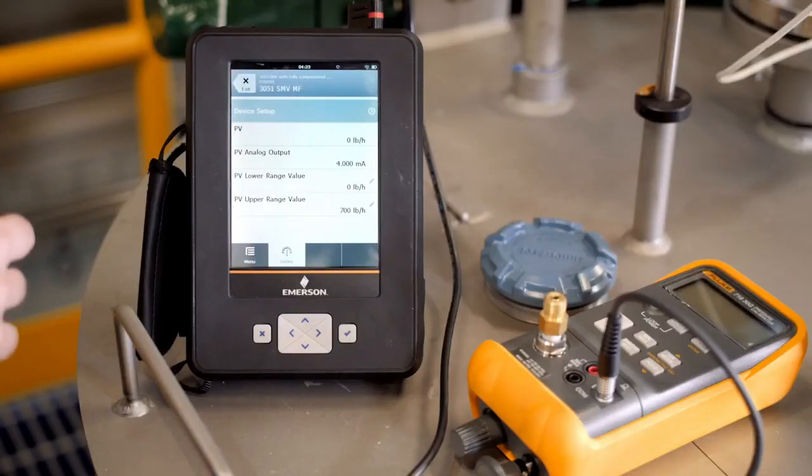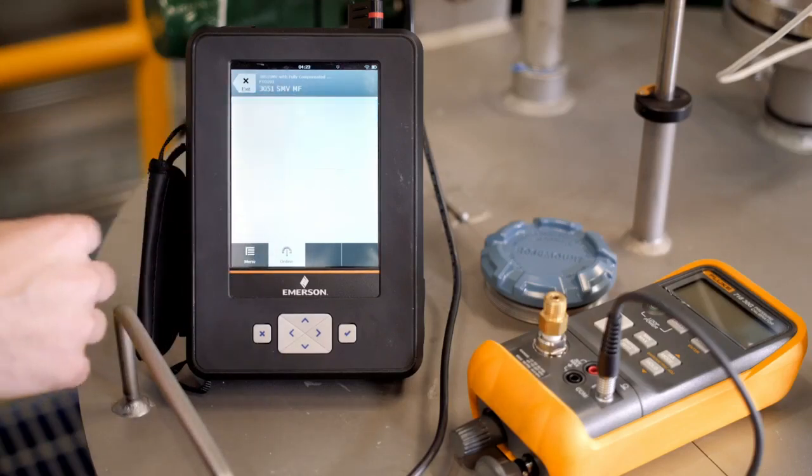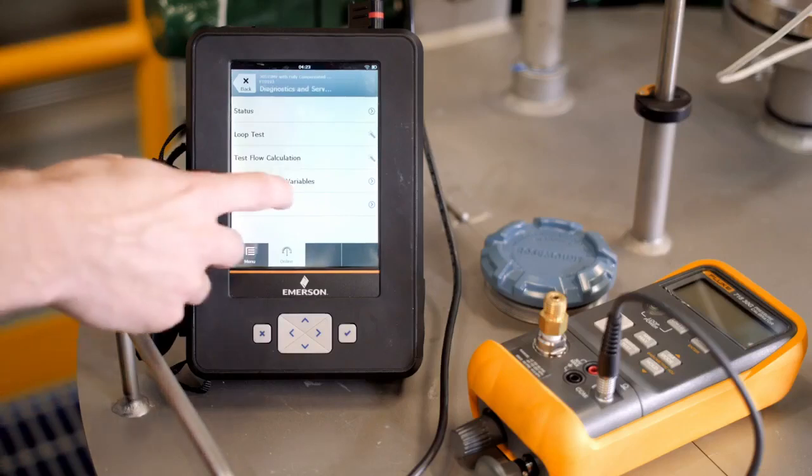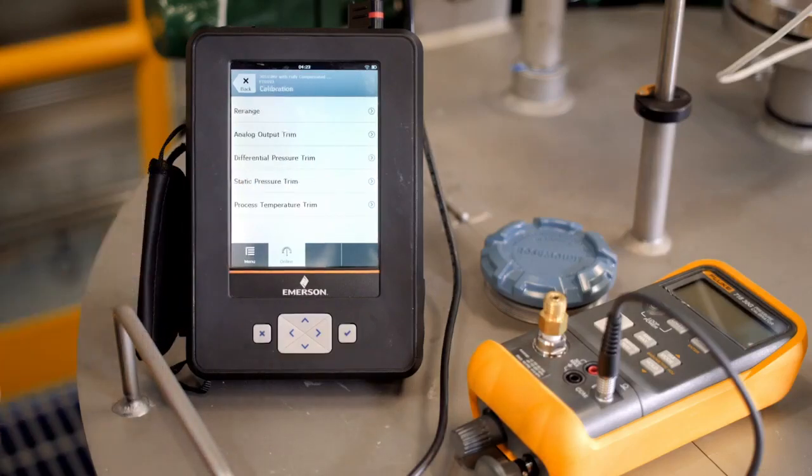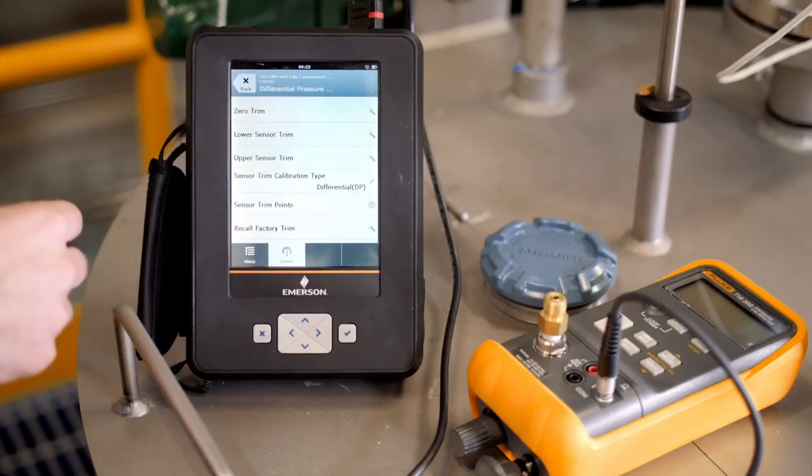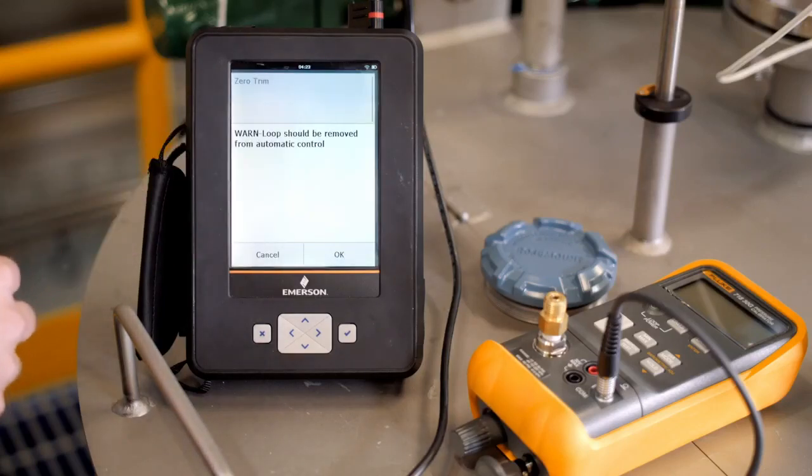To access the zero trim option on the Trex, first find the calibration page. Now select differential pressure trim, then select zero trim. Once you have accessed the zero trim menu, follow the guided wizard. Once each step is complete, zero trim has been successful.